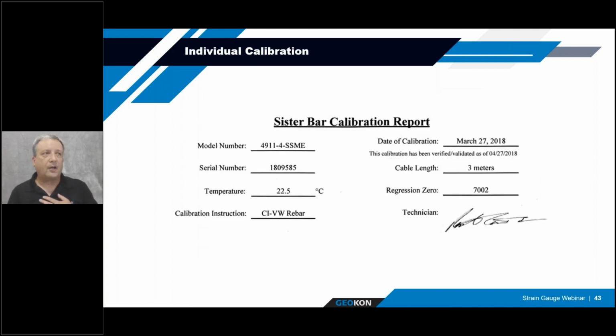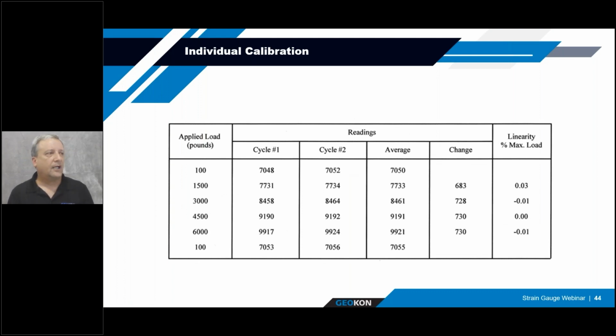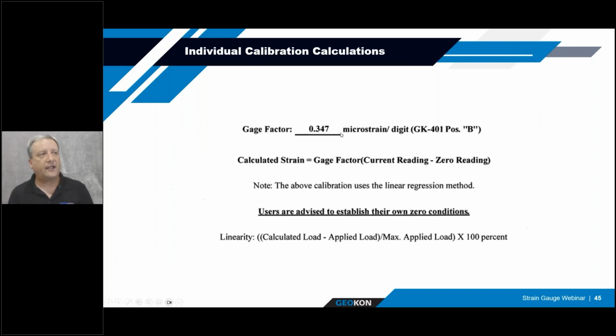The sister bars, however, are individually calibrated. That's the one exception. The sister bars are individually calibrated, and if you would prefer, instead of having a batch factor, you can have your strain gauges individually calibrated as well, at an additional cost. In those cases, you would get an individual calibration report for each instrument. The sister bars will definitely always have their own individual calibration sheet. They're loaded in tension up to about 6,000 pounds. The readings are typically output in microstrain. So from that, you get a linear gauge factor in microstrain per digit. Similar to what was described before, to get your calculated strain or change in strain, you'd have a zero reading and your current reading, and multiply the difference times that gauge factor to get your change in strain.